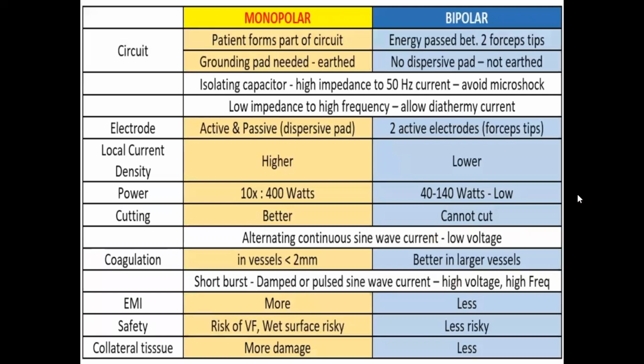So I have this in my own notes, where I have incorporated all the potential MCQs in tables. So, circuit: in monopolar, the patient forms part of the circuit, and a grounding pad, which is the earth plate, is needed. But in bipolar, energy passes between two forceps tips, no dispersive pad, not earth. Both use an isolating capacitor, high impedance to 50 Hz current, to avoid microshock.